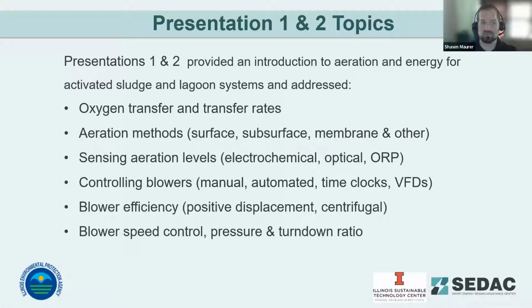To review our first presentation on aeration efficiency: we touched on oxygen transfer and transfer rates, the different aeration methods such as surface aeration devices, membranes, and diffused aeration on the bed of a basin, sensing oxygen levels through different types of sensors, and controlling blowers through time clocks, VFDs, and manual versus automated processes. We're going to dig a bit more into that control in this presentation. We also looked at blower efficiency — positive displacement versus centrifugal blowers — and keeping an eye on your turndown ratio so you can optimize efficiency when operating at less than design load.